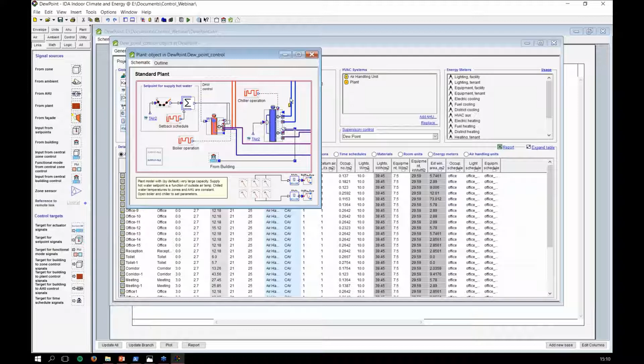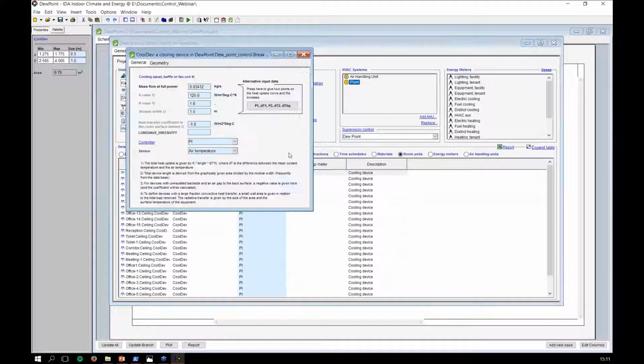Maybe you should mention that you have replaced the ideal units with the water-based units. Yes, I should mention that. Two things I did from my base model. The first is I turned off the cooling coil in the air handling unit because I want to use just the cooling panels to cool down my rooms, and I want to see the effect on COP, which will come later on. The second thing was that all the room units, which by default are ideal coolers and ideal heaters, I replaced the ideal coolers all by chilled beams, sized typically 500 watts, just by default. So now the cold water going to the zones is going to those.